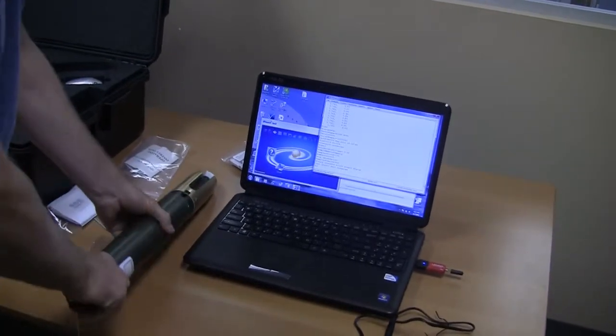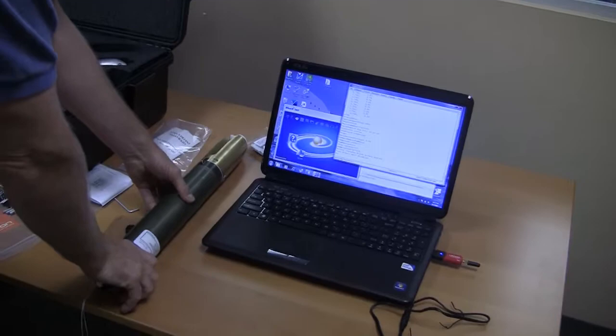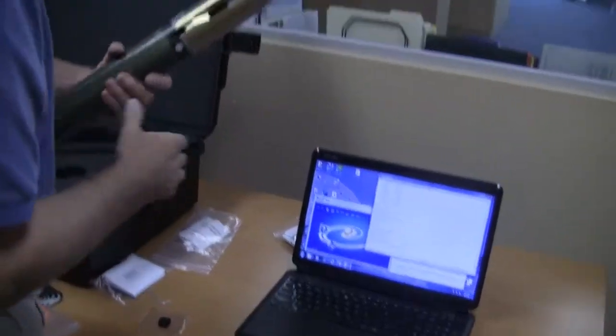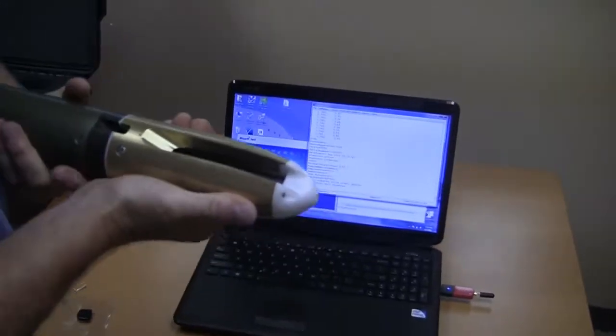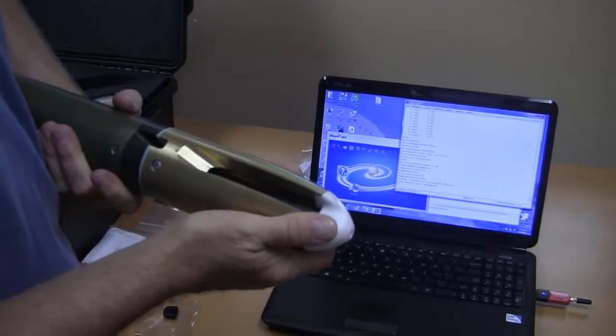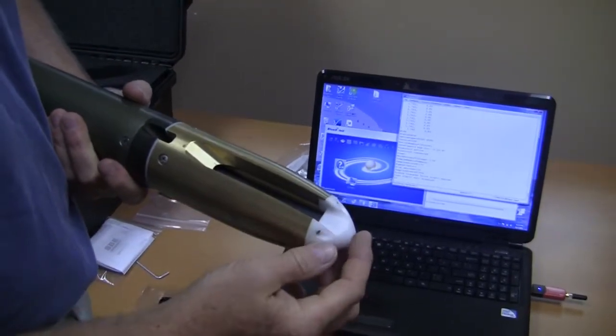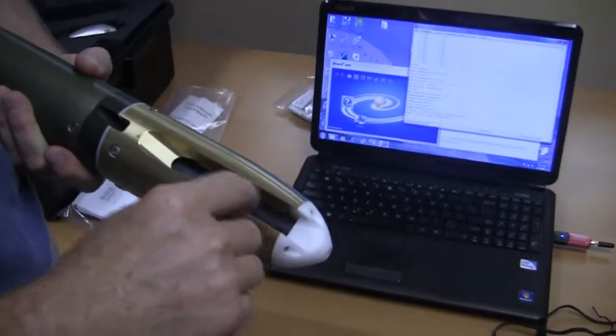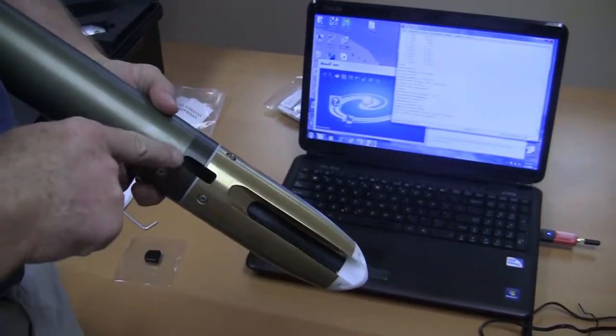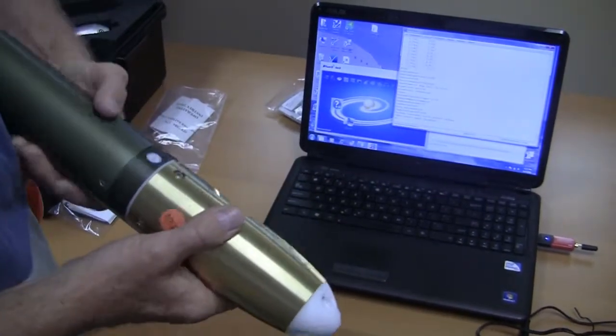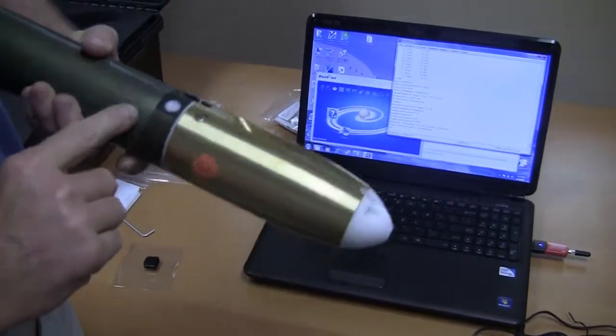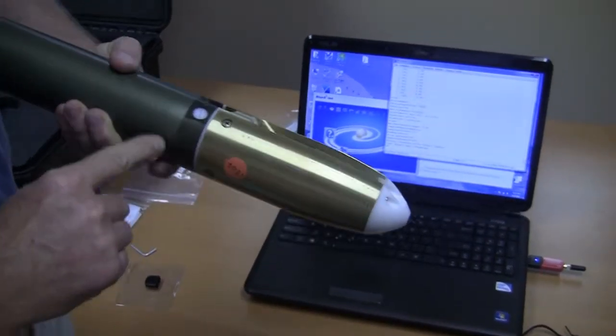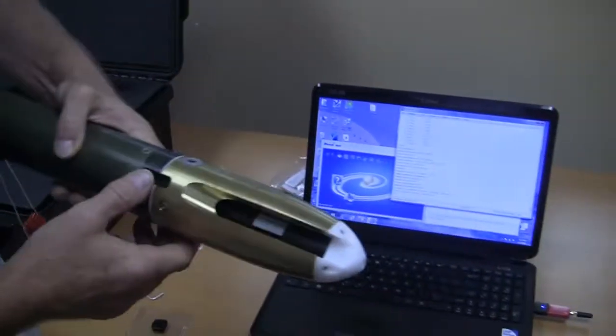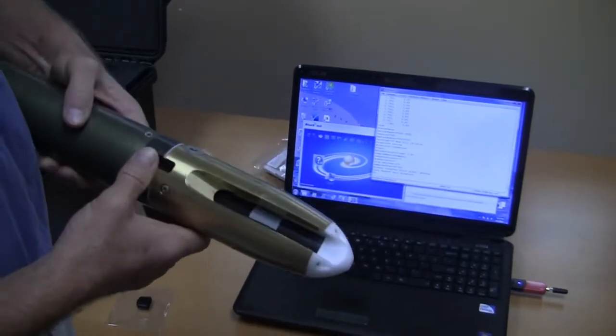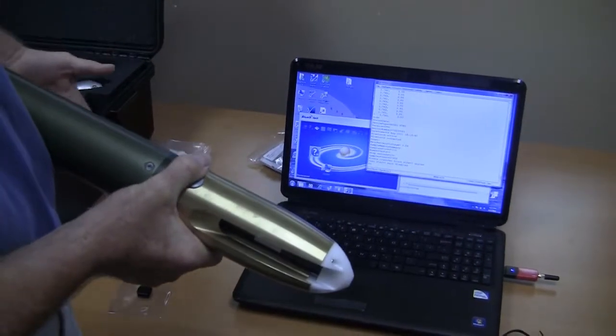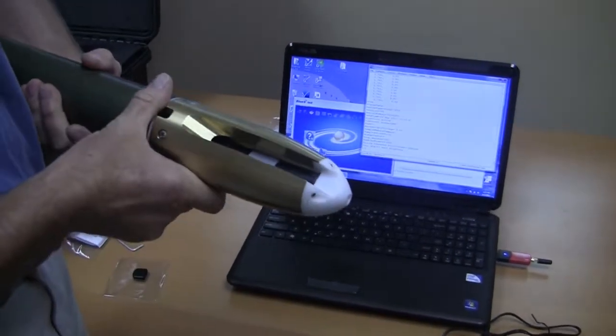Generally, just one remark with regard to maintenance. It is important to keep the sensors clean, and that involves rinsing them with fresh water after use in salt water. This is the conductivity cells, especially this one has to be kept clean, so just rinse fresh water through here. And occasionally make sure that the screws are tight around here, and the pressure case up there. And ideally you want to air dry the probe before you store it in a case in order to prevent it from growing mold.